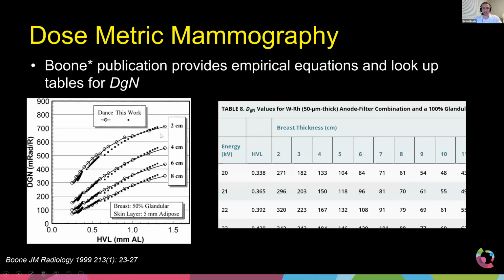So Boone provided all of these empirical equations. You could actually use these equations if you wanted to create your own calculation model, your own software. You have these equations that you could build into it. The equations are based off of breast thickness and the machine half value layer, or the beam quality.